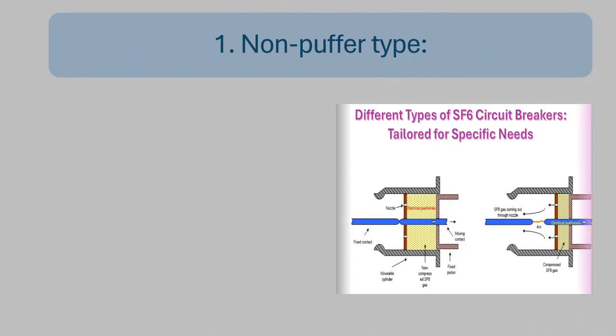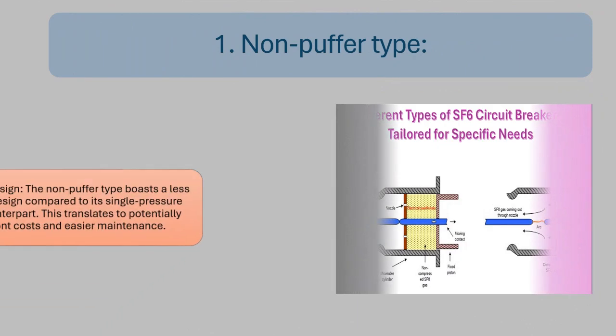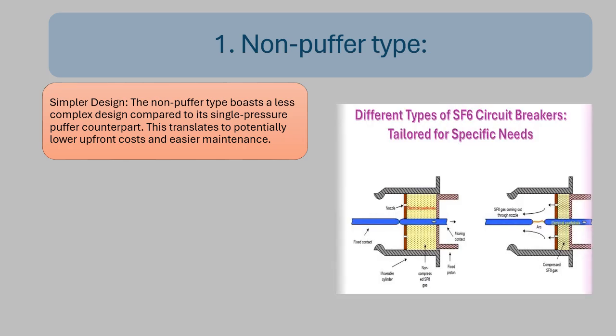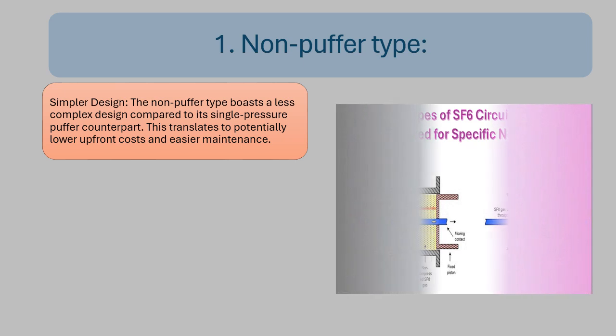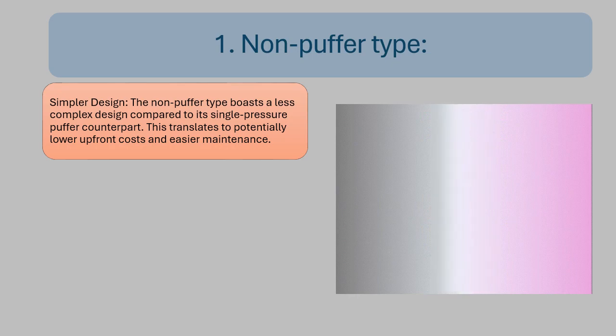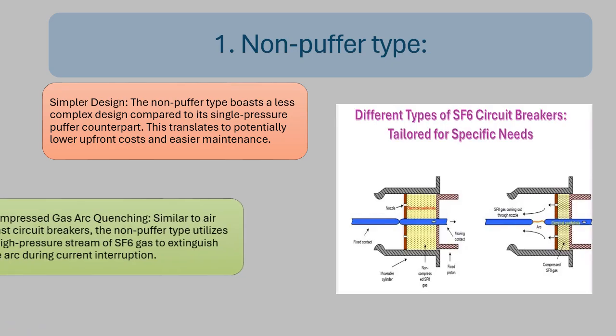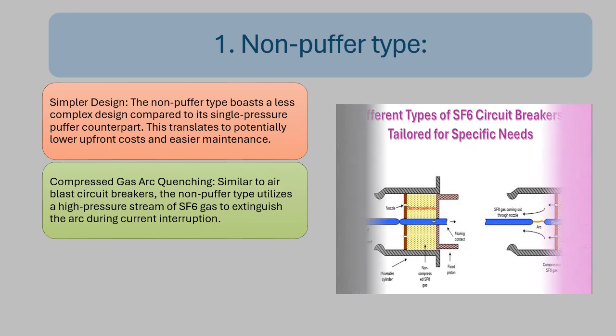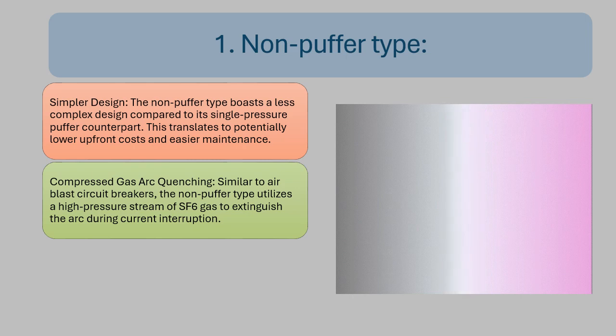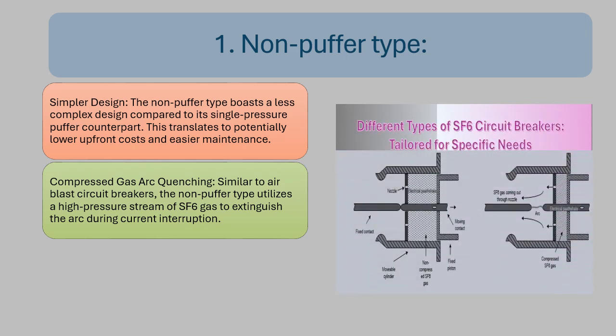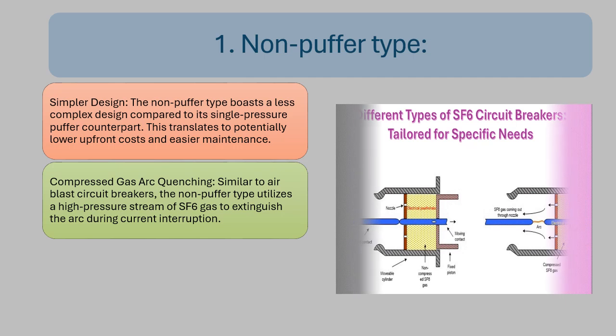First, the non-puffer type, a simpler design. It boasts a less complex design compared to its single-pressure puffer counterpart, translating to potentially lower upfront costs and easier maintenance. For compressed gas arc quenching, similar to air blast circuit breakers, the non-puffer type utilizes a high-pressure stream of SF6 gas to extinguish the arc during current interruption.